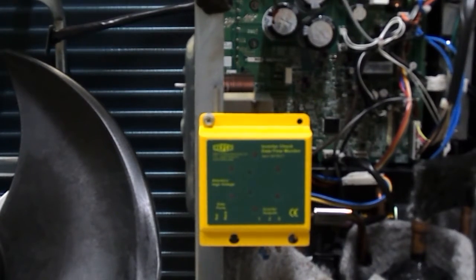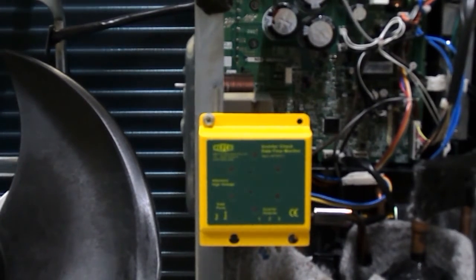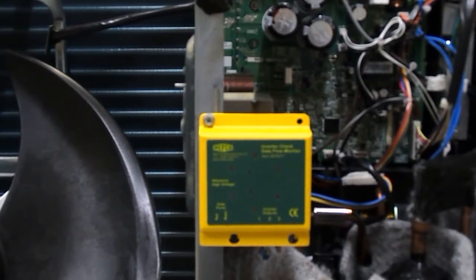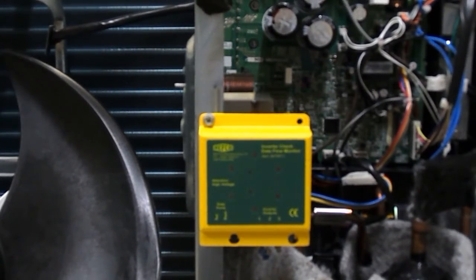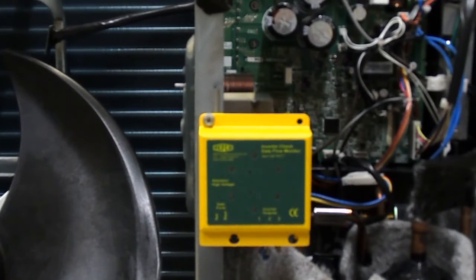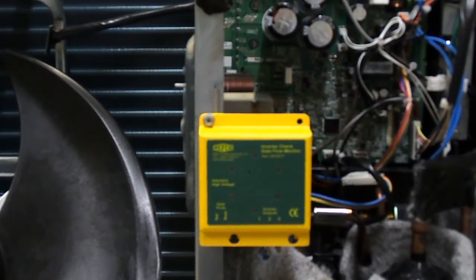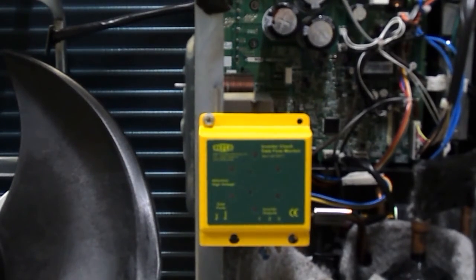What it doesn't tell you, and what I should point out, is that it doesn't tell you if the unit is outputting correct voltages. We know that they're switching in correct symmetry and order and we don't see an obvious problem, but what it's not actually telling us is if the voltages are even.